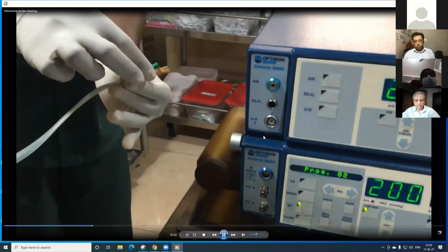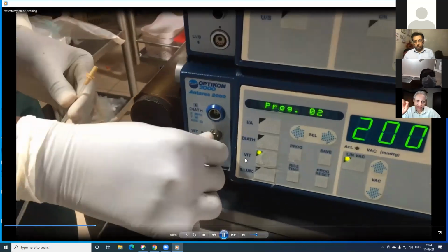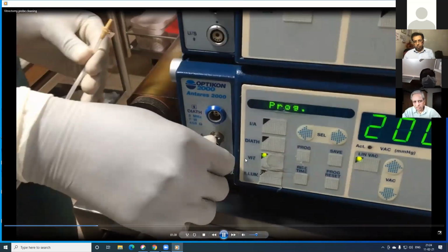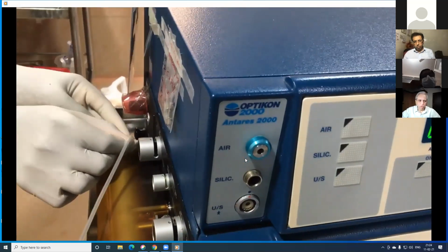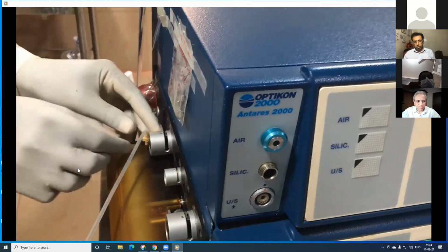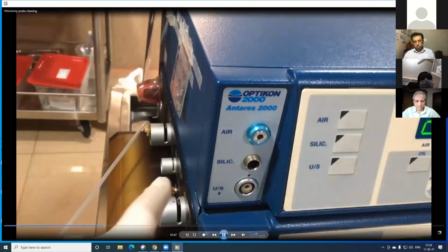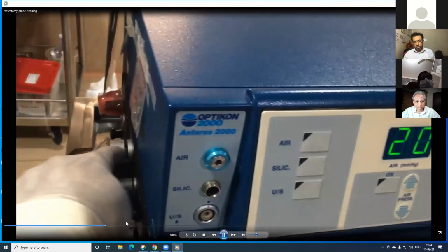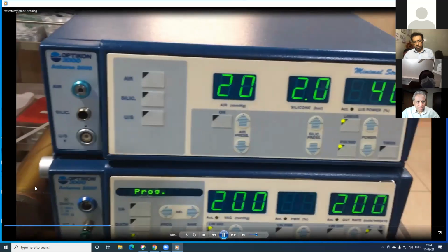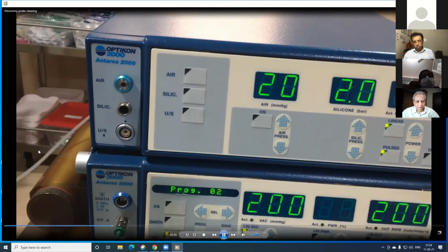So how do you identify? There are two connectors to the probe. The cutter is in the center. The peripheral outlet on the probe is for the vacuum. This is an autoclavable vacuum collector. This is made of polycarbonate. That's a lid there. You can discard it, or you can collect the specimen in case you're collecting it for culture and sensitivity. And then the entire thing can be autoclaved.